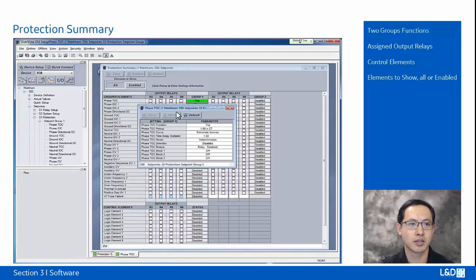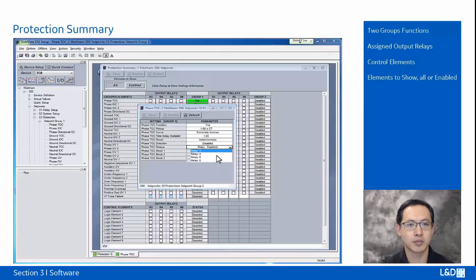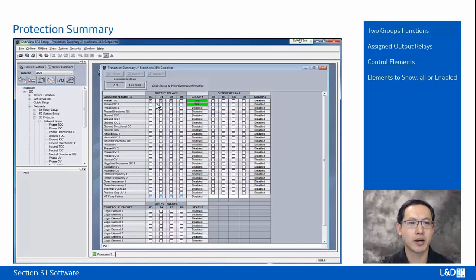So we can start the Phase TOC, and under Phase TOC we can select the output relay. For example, I choose 3, 4, 5 and click Save. Close this setup screen. Now I can see from this summarized screen the relays R3, 4, 5 being checked. So that's a very useful tool.